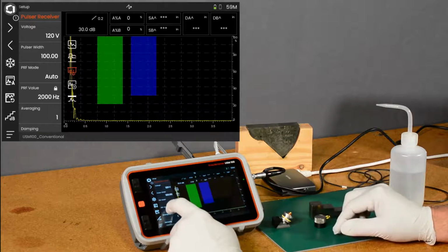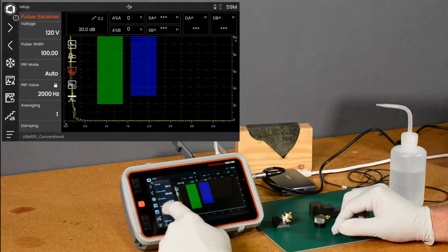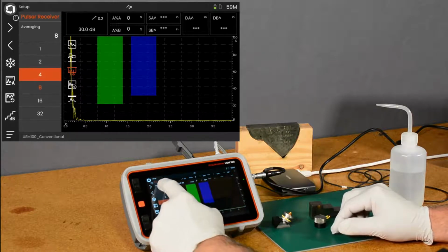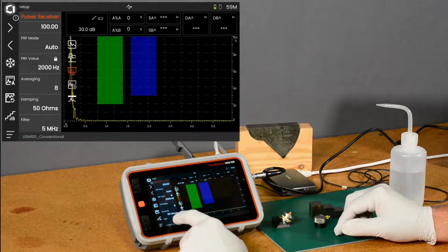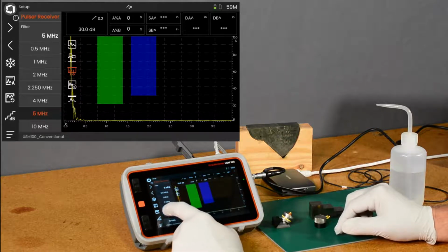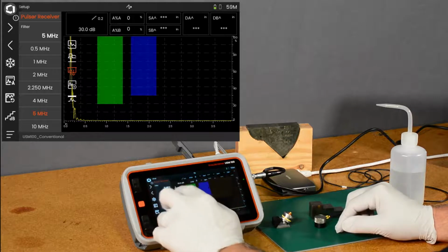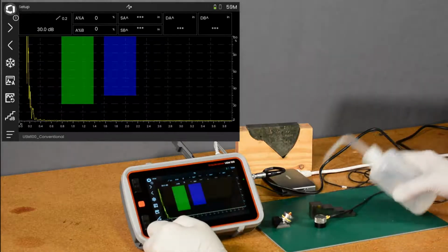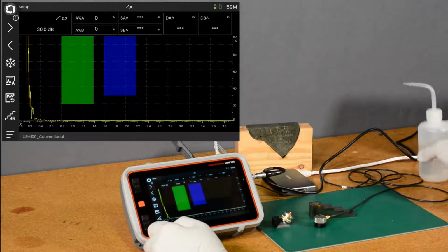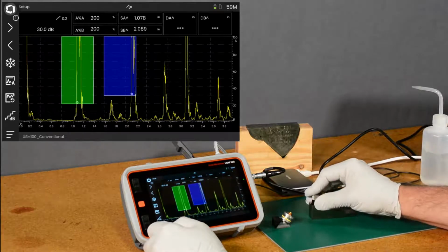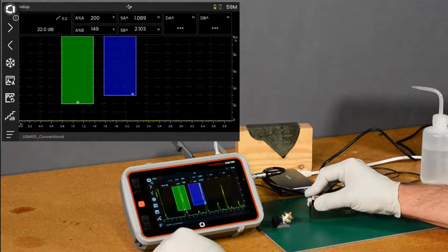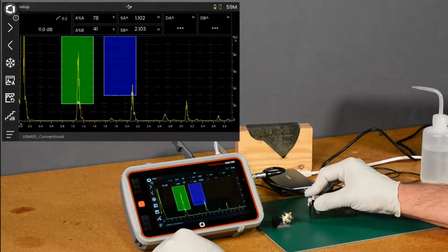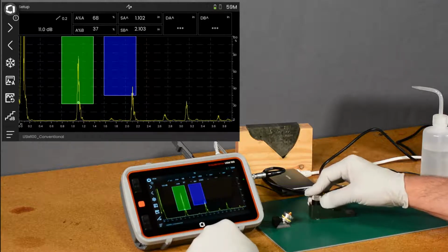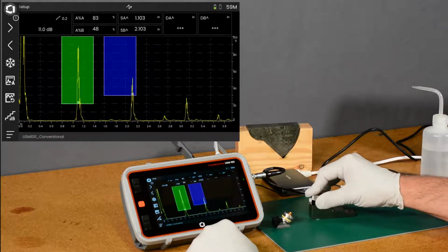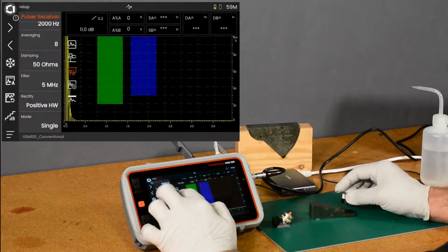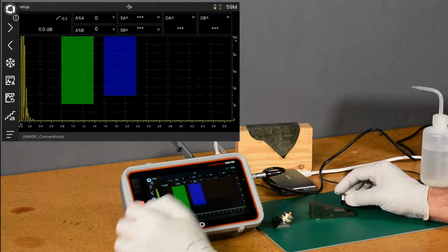The filter selections are over here in the UT menu, and we see that's already set to 5 megahertz. So we're in a good starting point. Let's put a little coupling on our block, and we'll just look at 1 inch here. So we can take our gain down some. We'll use the auto 80 function to get the gain on the 1 inch block in gate A nicely at 80%. Let's close that, and we'll go to our 2-point calibration menu.